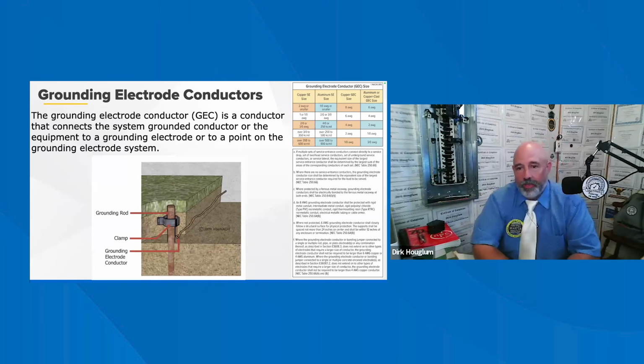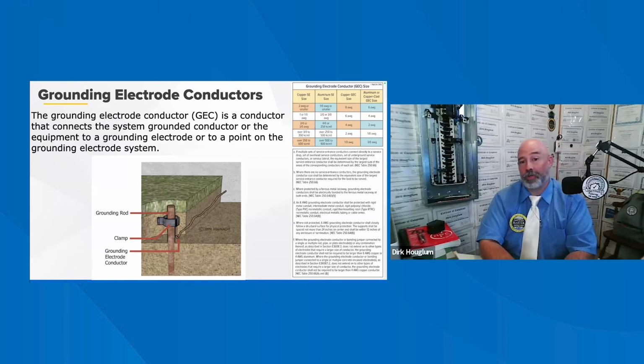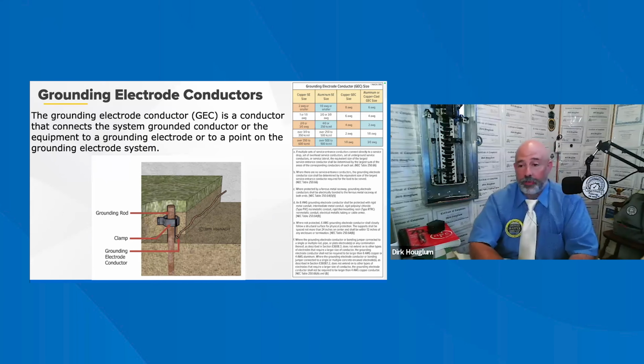I love this picture. The grounding electrode conductor, the GEC, is a conductor that connects the system grounded conductor or the equipment to the grounding electrode or to the point of the grounding electrode system. The GEC is copper, aluminum, or copper-clad aluminum. It is not intended to carry current except in case of a ground fault. It can be bare and without color. Its size is related to the amperage of the service entrance. Okay, so the table below will show you the sizes of the grounding electrode conductor here.